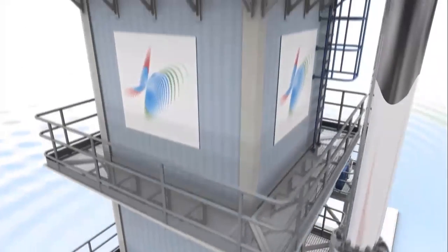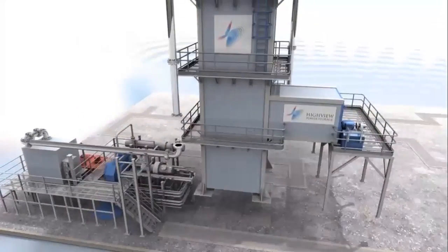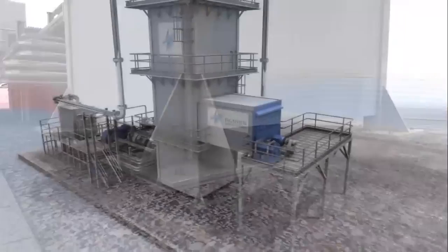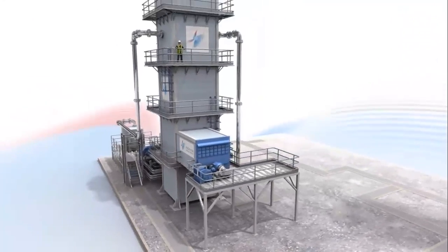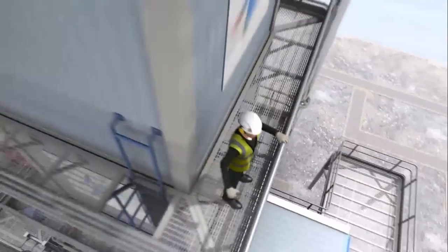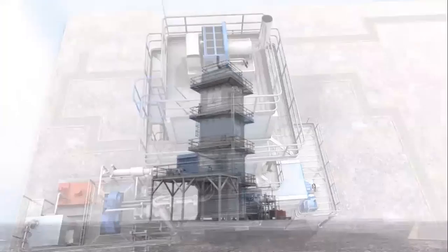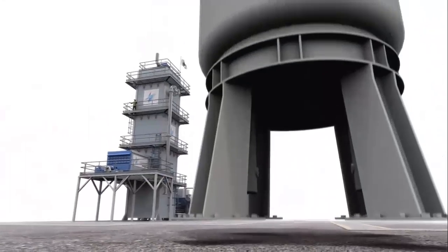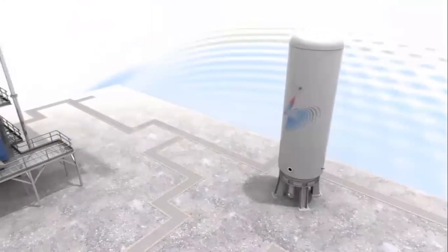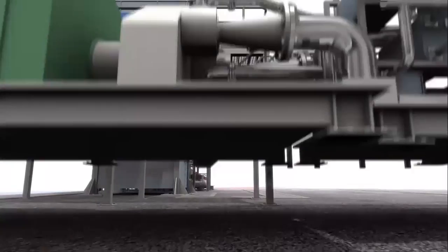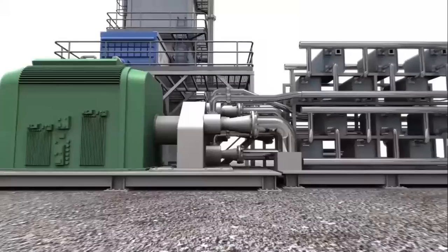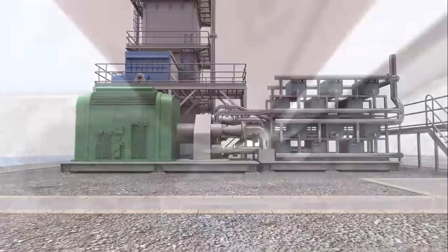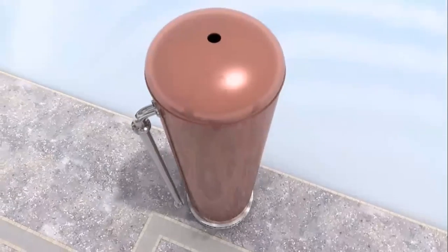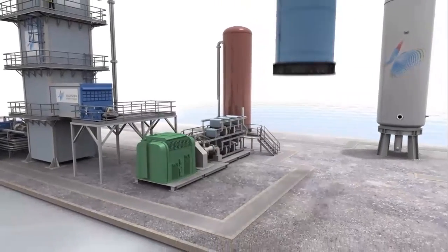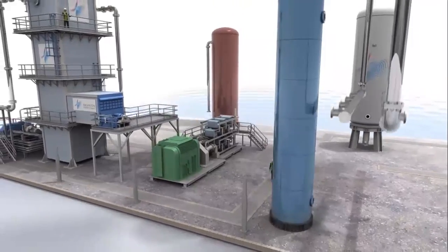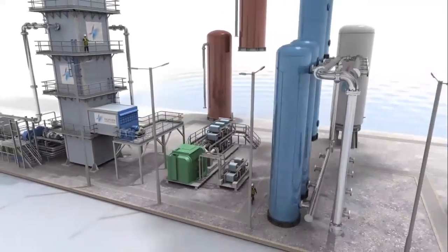Highview's liquid air energy storage system consists of three main components. A charging device, which uses off-peak or excess electricity to power an industrial liquefier which produces liquid air. An energy store where the liquid air is held in an insulated tank at low pressure, and a power recovery unit where regasified liquid air is used to drive a turbine and generate electricity. Operating efficiency is enhanced by adding a thermal store and our proprietary cold store. These capture and store waste cold and heat from the process.